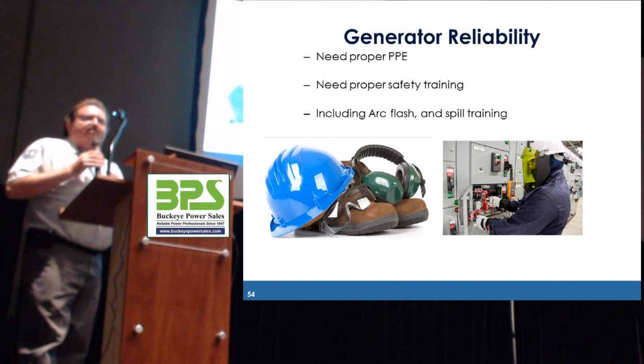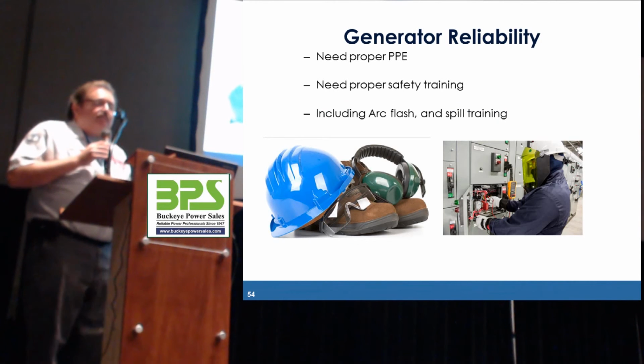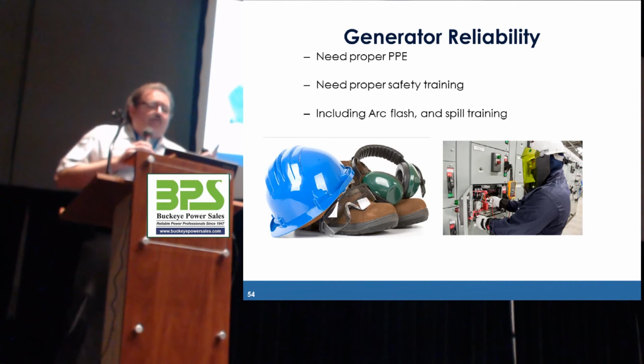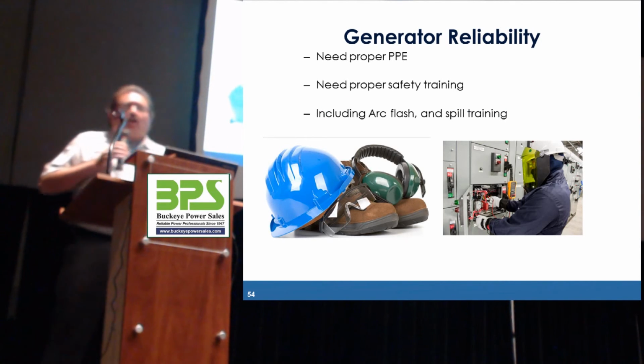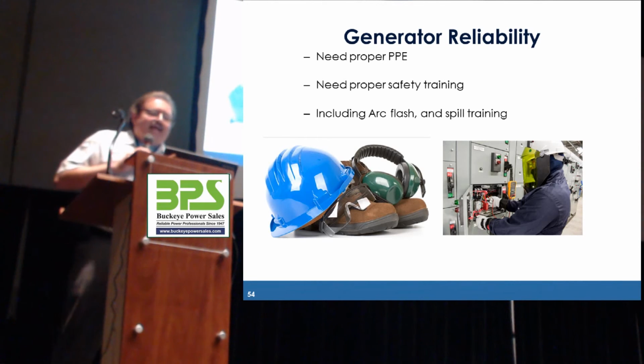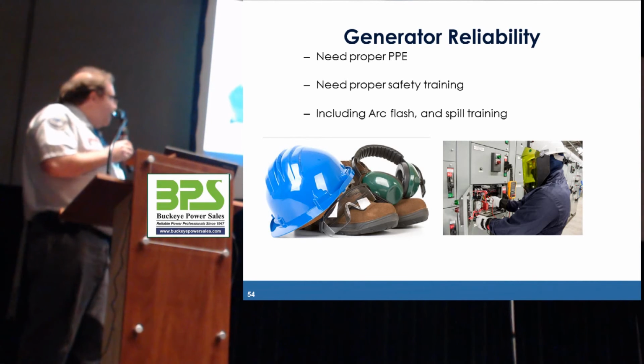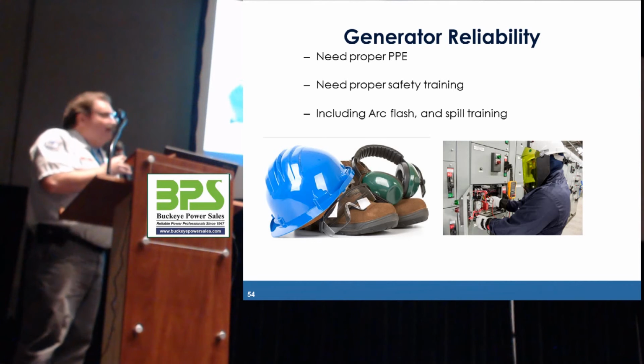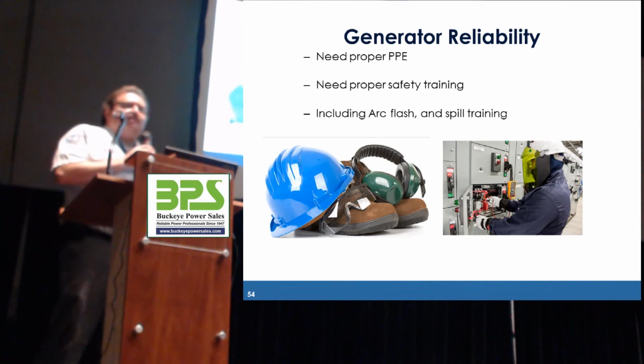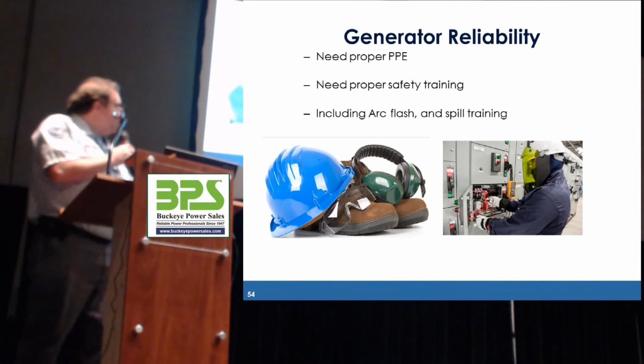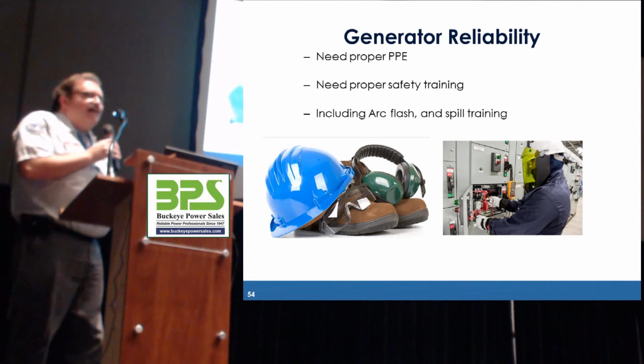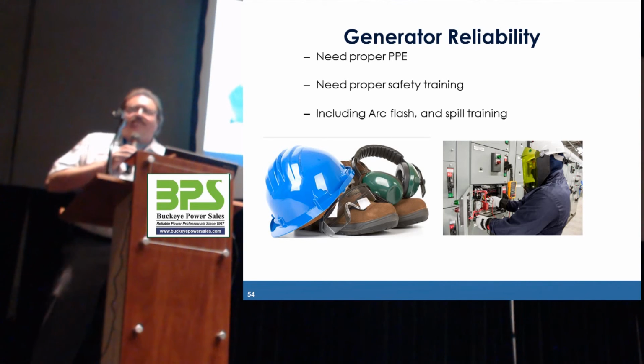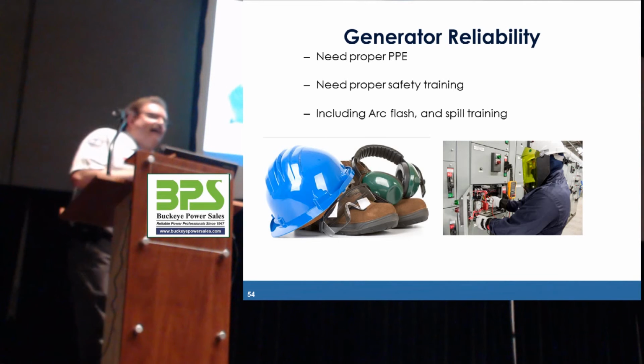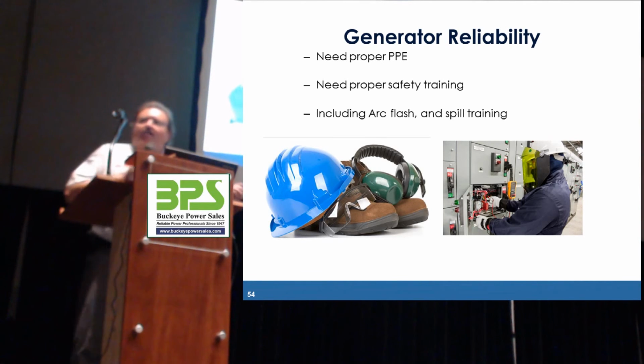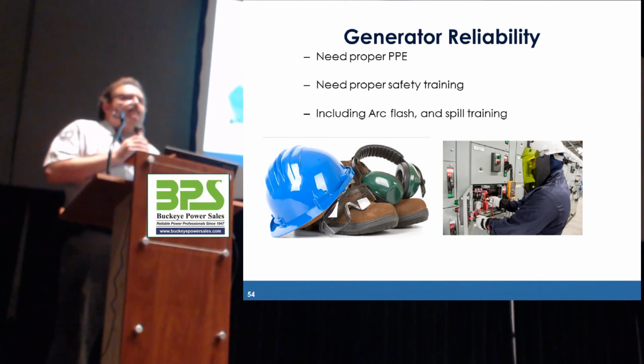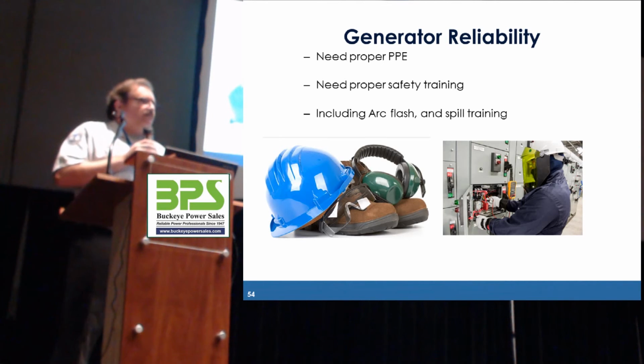The people that we touched on this, you have to have that proper PPE. They need to have proper safety training, which includes arc flash training and spill training. So as we touched on, you cannot work on things hot, but you can test with a meter, but you have to have your full arc flash gear. Again, the arc flash gear is not there to make it so you can work on it hot. The arc flash gear is there to supposedly make you survive the explosion.